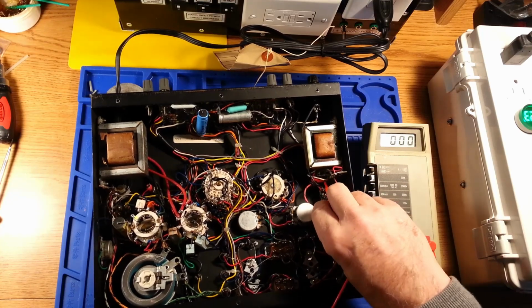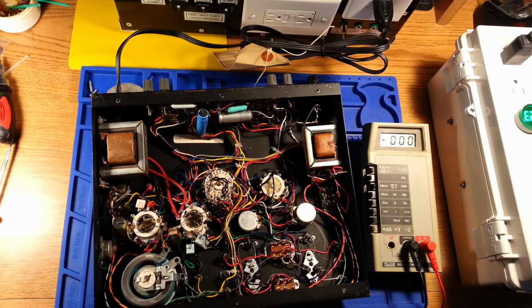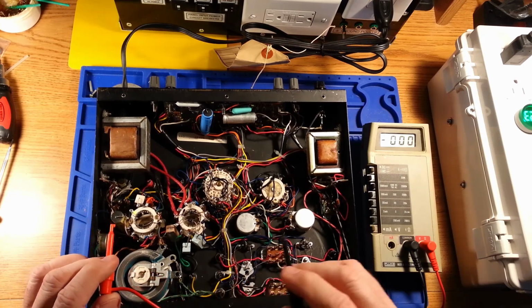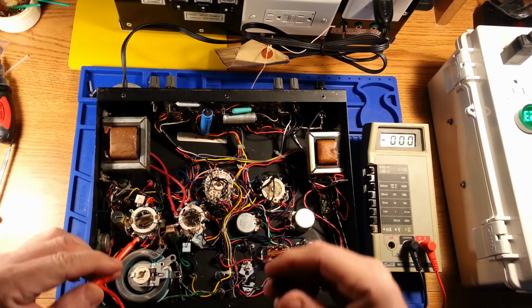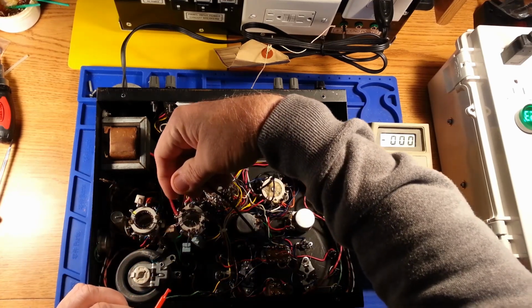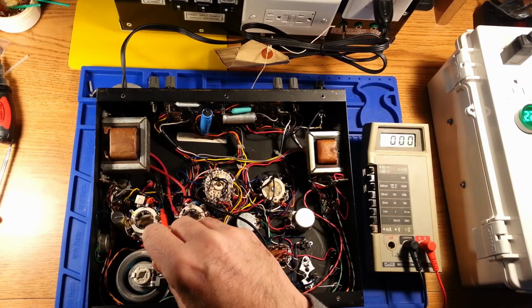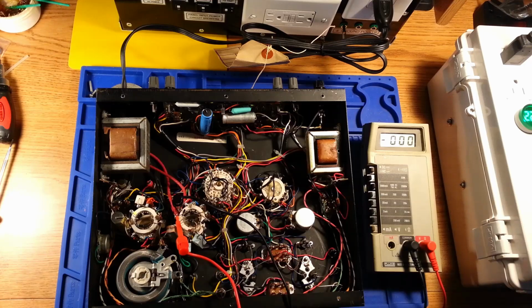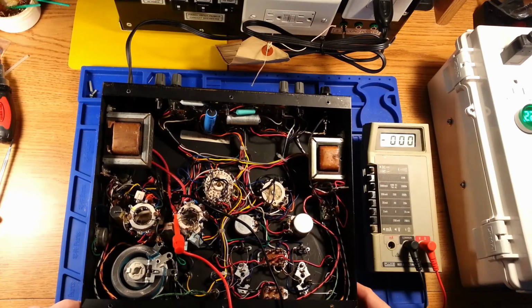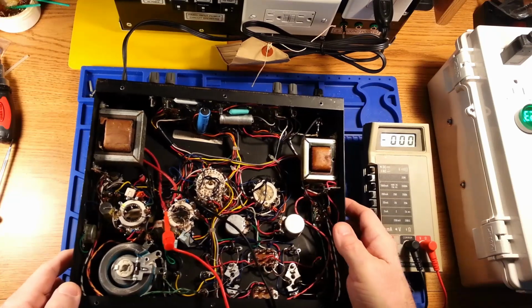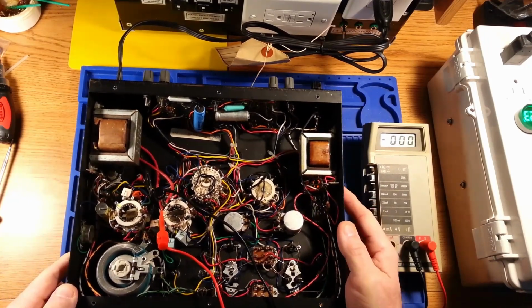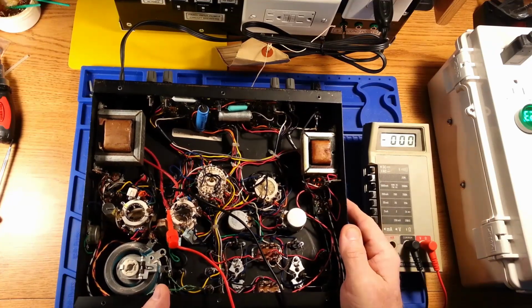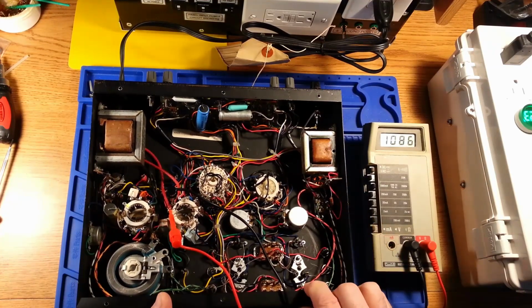I had to do some research and tinkering with this thing. I found that this only has an output when the push button for peak inverse voltage is selected on the front of the panel. It is depowered until then. I'm going to make all my connections one-handed, one at a time. And now I am going to turn the unit back on. And then I'm going to energize that transformer, hopefully with the peak inverse voltage button.